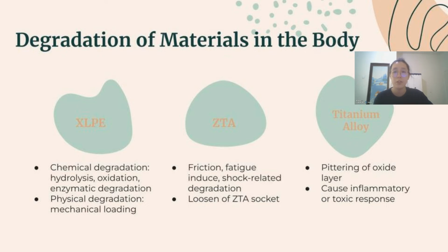The titanium alloy is covered with a thick titanium oxide layer to prevent corrosion. However, as time goes on, the oxide layer may be mechanically removed or loosened due to metallic debris, which is caused by extreme positions achieved during gait routine. The wear particles caused by degradation may lead to inflammatory or toxic response, even though the bulk materials are biocompatible.